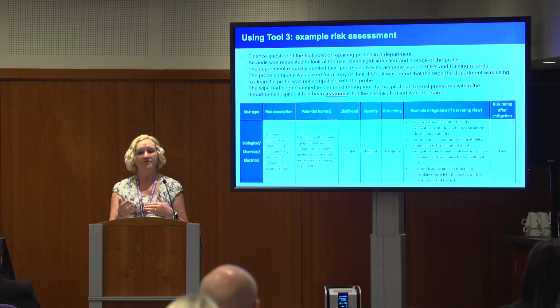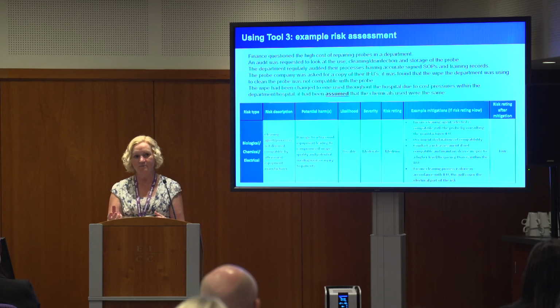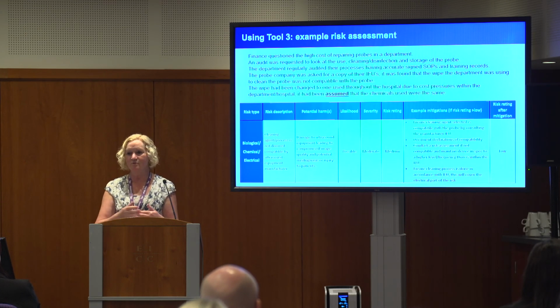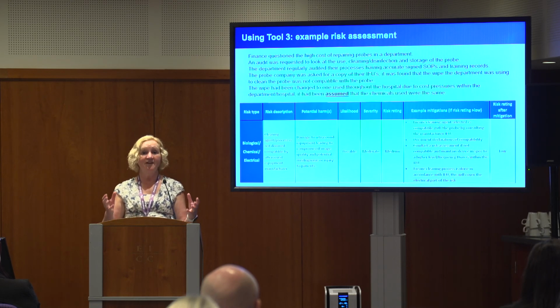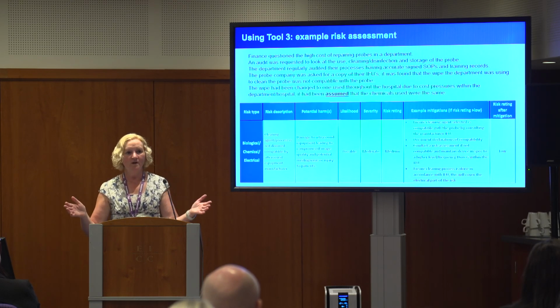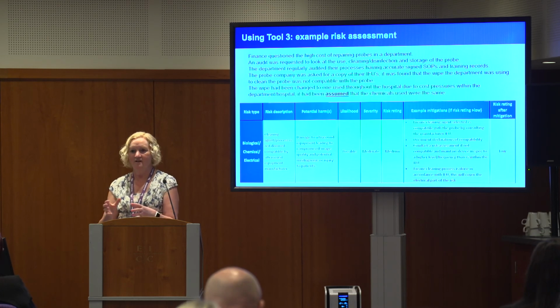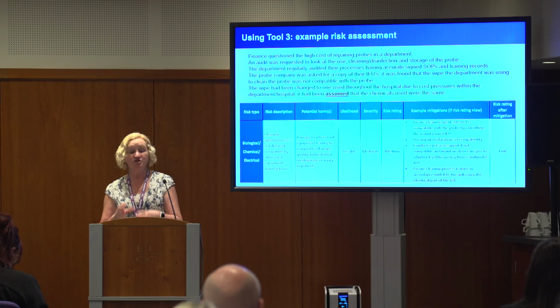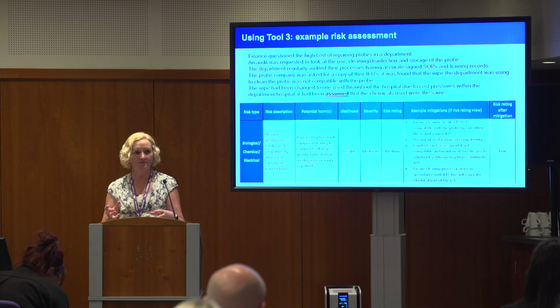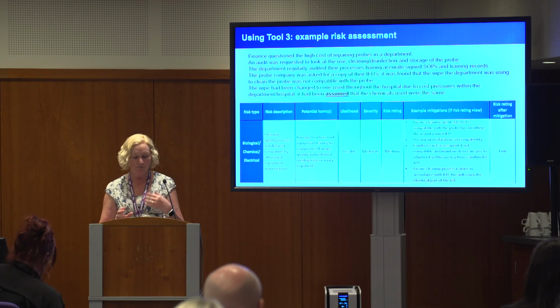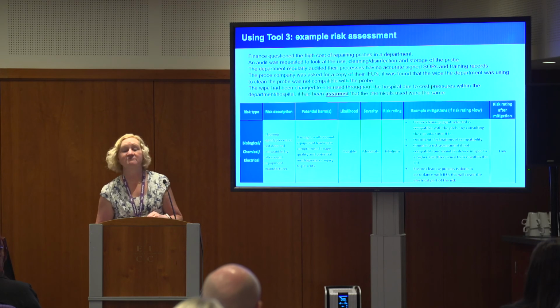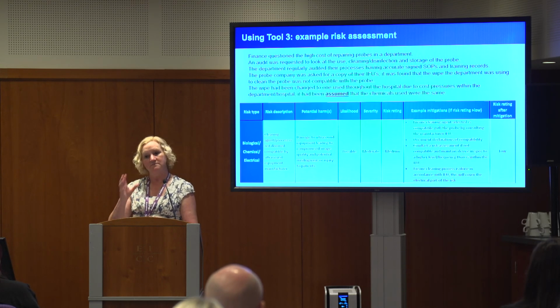When we'd sent off for the IFUs, we found that the chemical they were using wasn't compatible with the device, and that was what was causing the problems. And it was the fact that the hospital as a whole had been told to change their wipes to a cheaper wipe, and everybody had assumed it was the same chemical composition. It wasn't, and that's what caused the problem. So we did this risk assessment, changed the chemical back, and the problem seemed to alleviate itself.